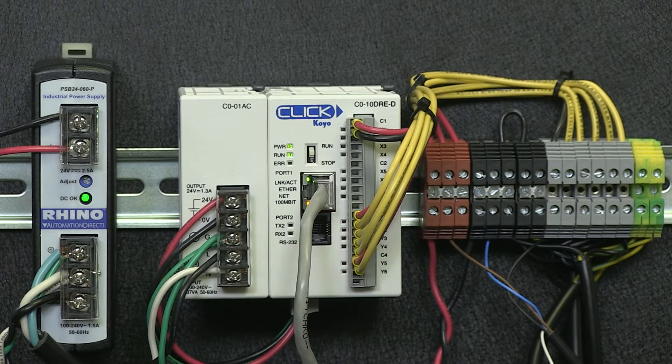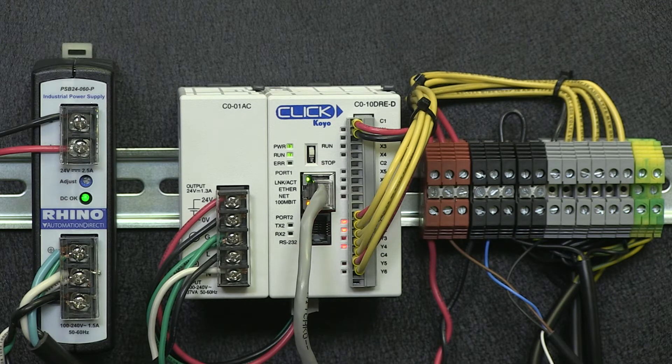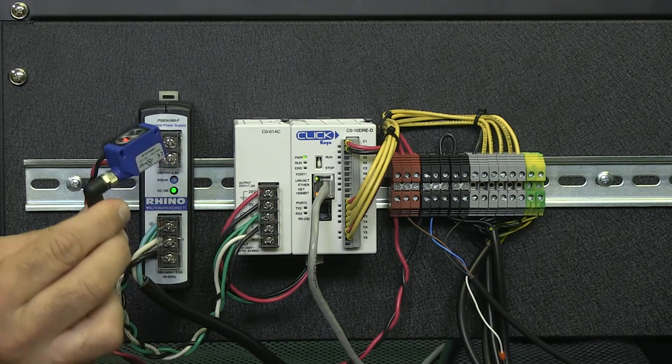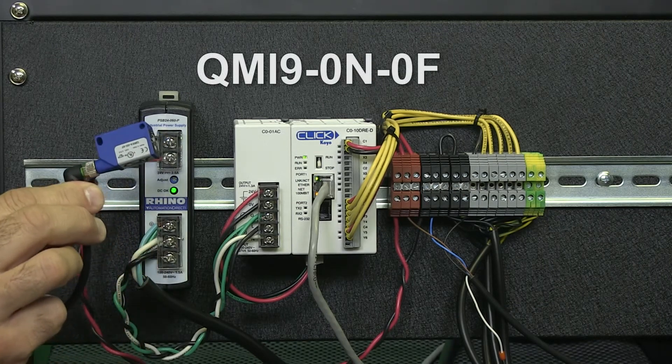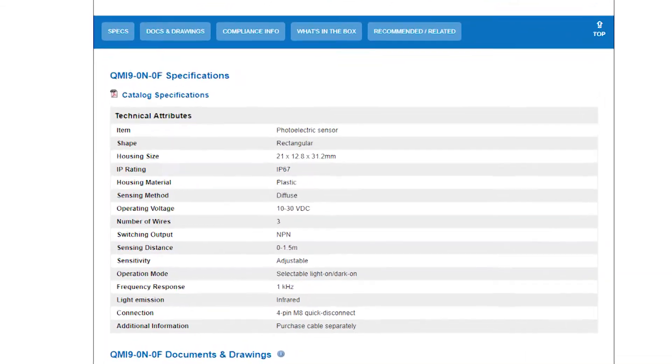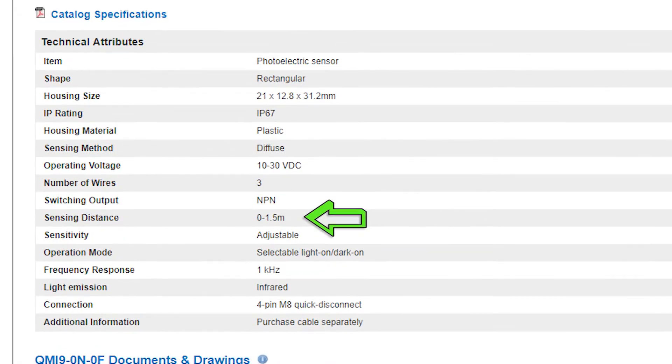Each valve is wired to an output on our PLC. I used Y1, Y2, Y3, and since the mail slot has an extend and retract it uses Y4 and 5. I chose a plastic housing photo sensor, part number shown. This DC photo sensor has a sensing distance of 1.5 meters and does not require a reflector or a two-part sensor with emitter and receiver. The sensor is wired to our X1 input, it's the only input we have. So, let's turn to the software.